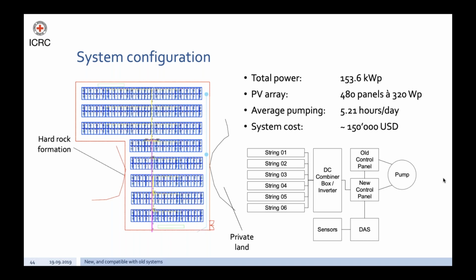Now I present you the final system configuration. The implemented PV system integrates existing infrastructure again, so the submersible AC pump can be powered by the solar system or alternatively by the grid or a backup generator. Therefore, it was required to keep the old control panel in place. The new control panel, however, is the master that allows choosing the power source automatically or manually.